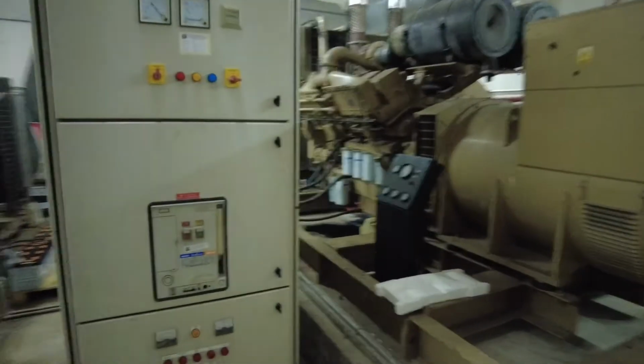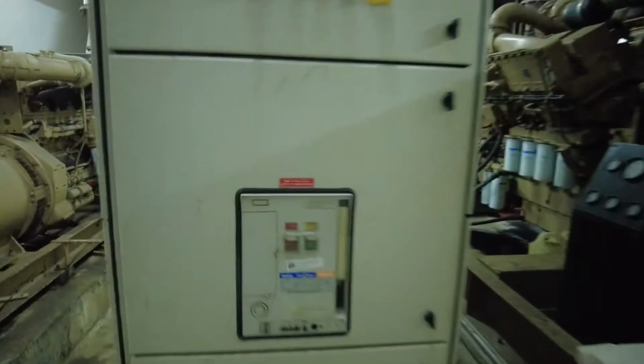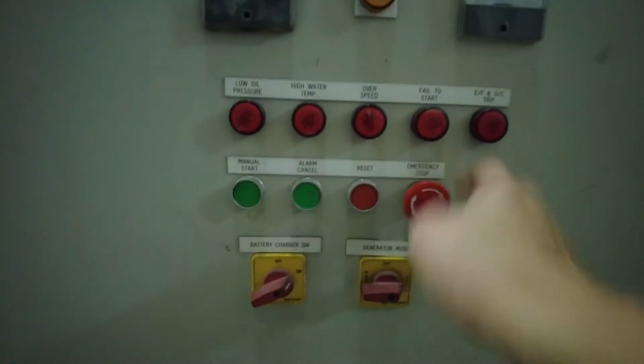Alright, then we check the AMF panel. Alright, this is the AMF panel. And here we have the ACB under on condition, auto mode, emergency stop release, because we are going to test run the genset under all auto mode. Charger okay. Alright. Then let's check the fuel. These two gensets, they share the same fuel tank. So they have two hoses here and they share the same fuel. So one diesel tank used by two gensets.